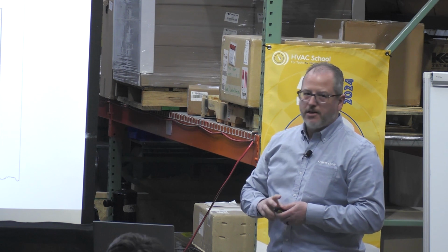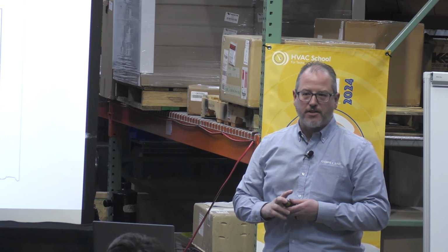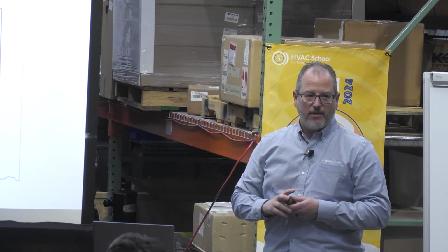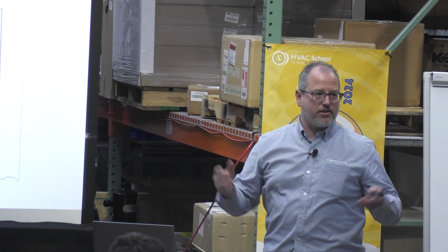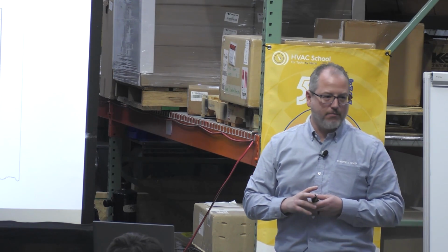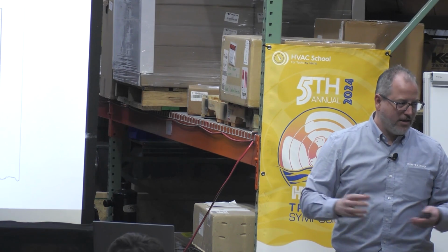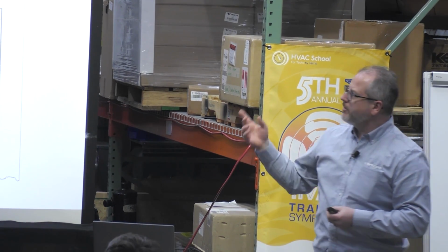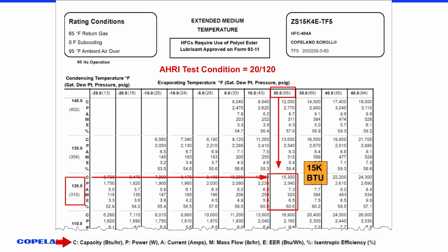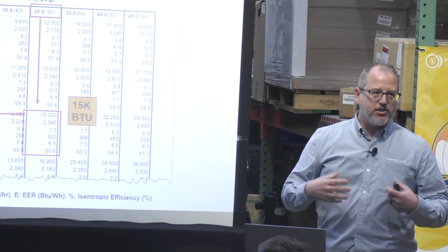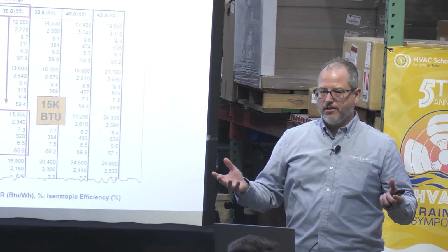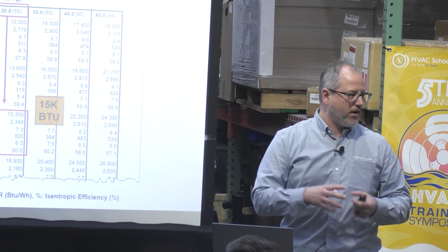That's what we get. Now, as the conditions change, do we always get the same amount of BTUs out of it? No. And in the refrigeration world, or in the air conditioning world, how often are our conditions the same? Never, right? So everything is always going to change. So when you look at a system, in this example, if you look way on the bottom of the page, it shows what all those letters mean. But the C is the capacity, P is power in watts, A is the amps. So as an example, amps on this one is 7.3. If we start changing things, our amp draw is going to change, right? So that's why we want to bring people to our apps.